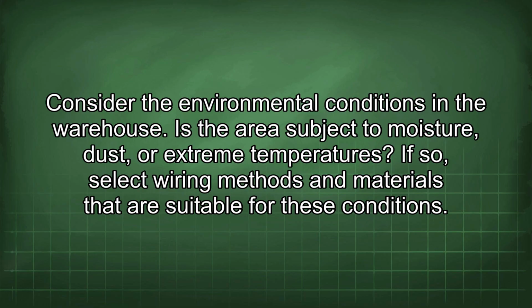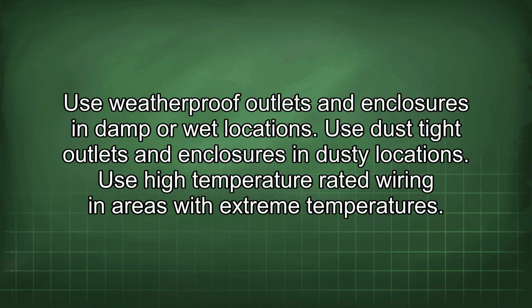Consider the environmental conditions in a warehouse. Is the area subject to moisture, dust, or extreme temperatures? If so, select wiring methods and materials that are suitable for these conditions. Use weatherproof outlets and enclosures in damp or wet locations. Use dust-tight outlets and enclosures in dusty locations. Use high-temperature rated wiring in areas with extreme temperatures.